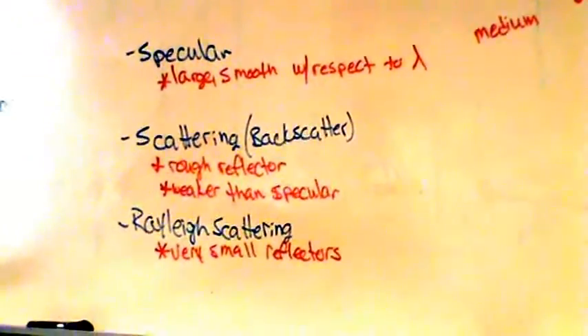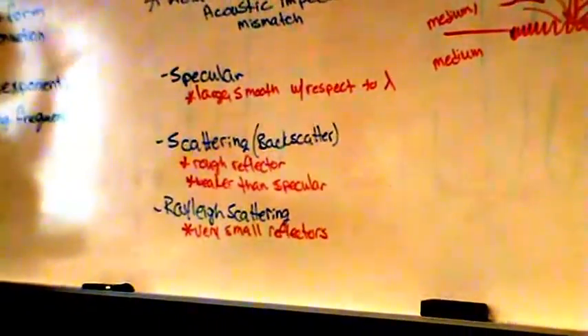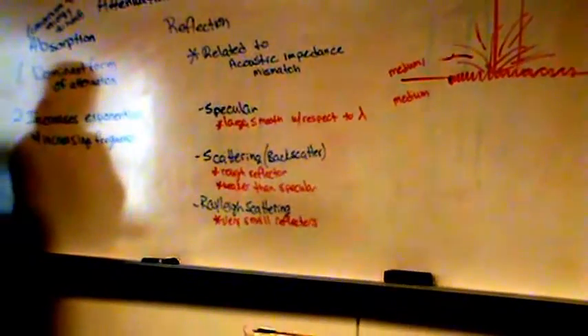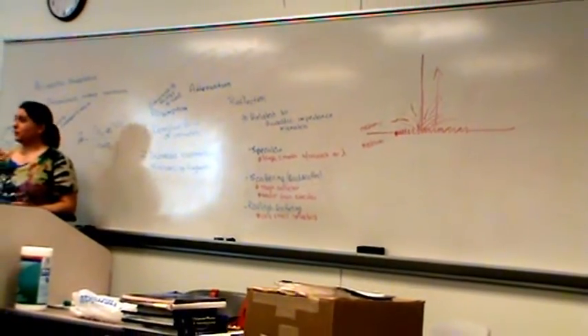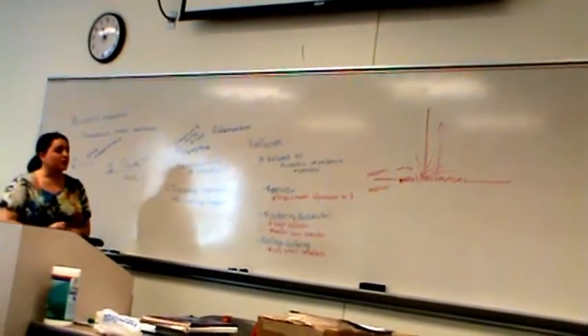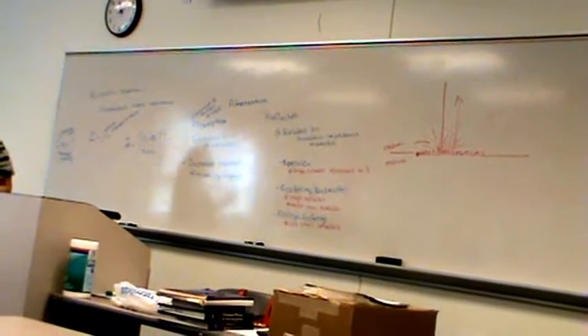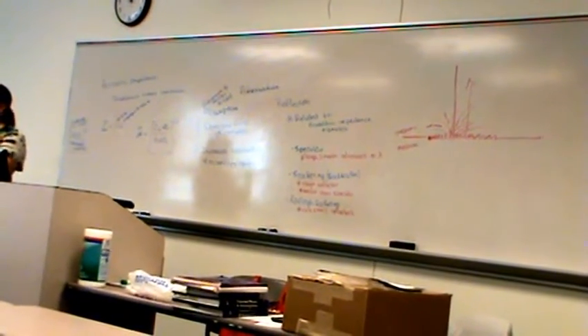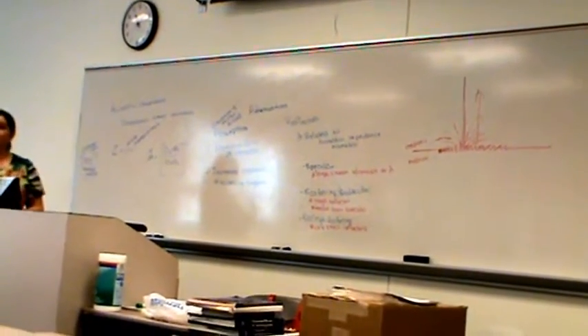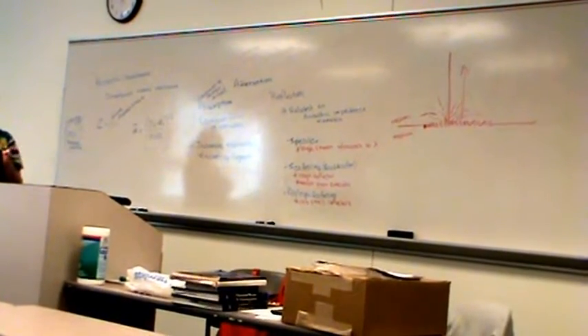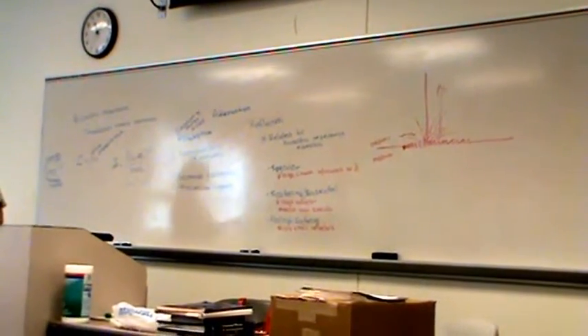For one, when you throw the tennis ball at that weird shaped brick wall, when it bounces off, it doesn't have as much energy as off a smooth, flat thing. And it also goes in all these different directions. So some of it is going to come back to the ultrasound transducer, but some of it's not. Some of it is going to scatter out in different directions. So it's weaker. And then Rayleigh scattering is even weaker. Remember, I gave the example of a tennis ball at a wall of pebbles, if I could suspend pebbles in the air. If I were to hit a pebble with the tennis ball, I might get a little bit of a reflection off the pebble, but I'm not going to get much. It's a very, very weak form of reflection. And there are an awful lot of chances where the tennis ball is going to fly right through the pebbles. So the ultrasound beam is going to fly right through these Rayleigh scatterers and not even be able to reflect off of them. So that's why it's a very weak form of reflection.